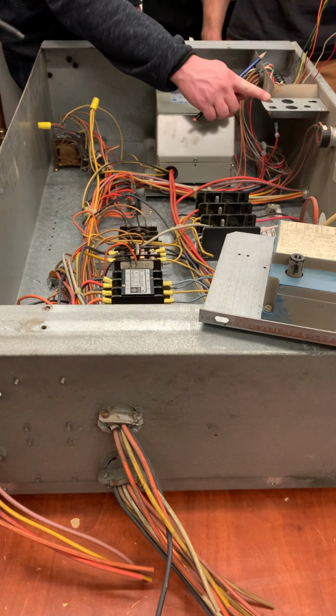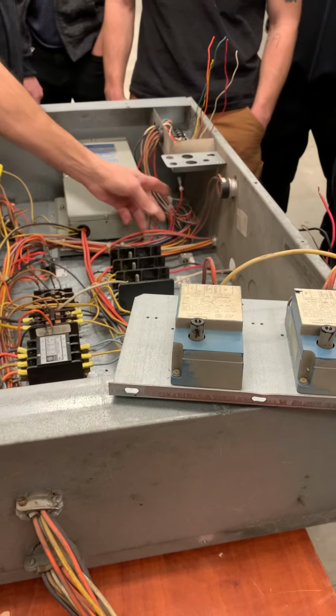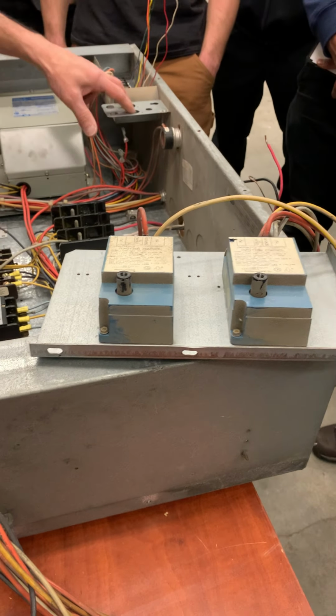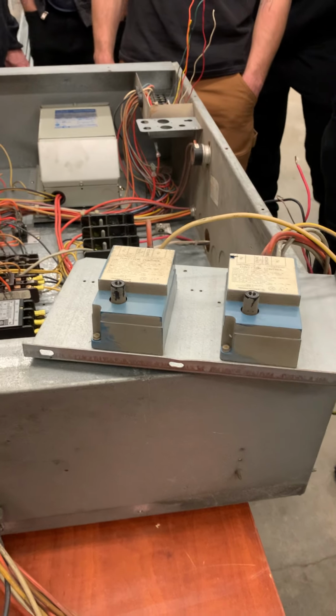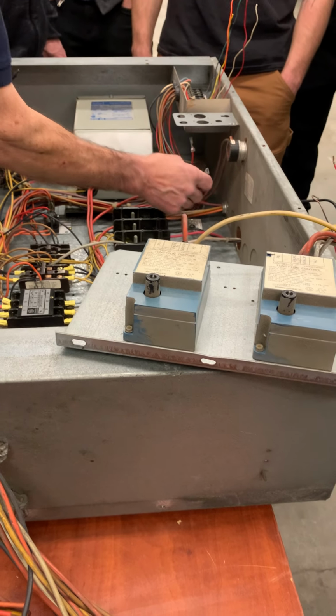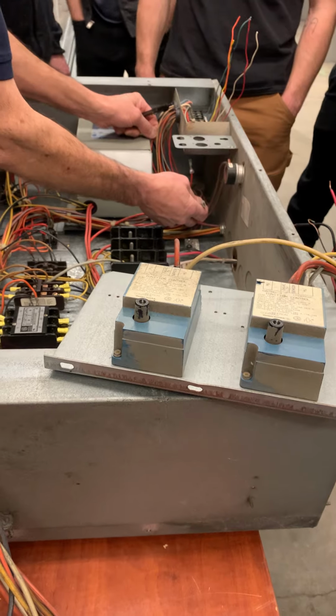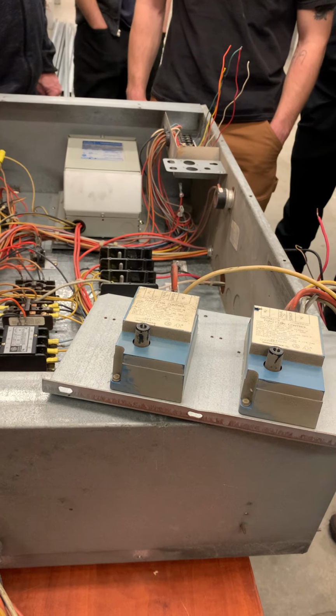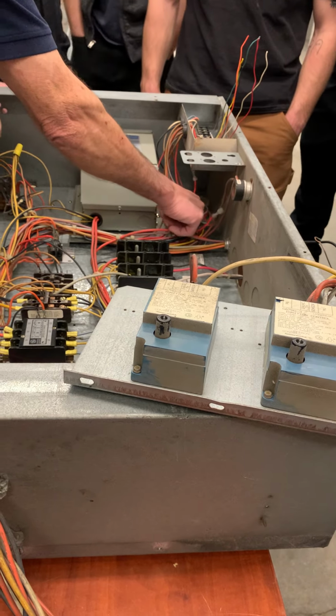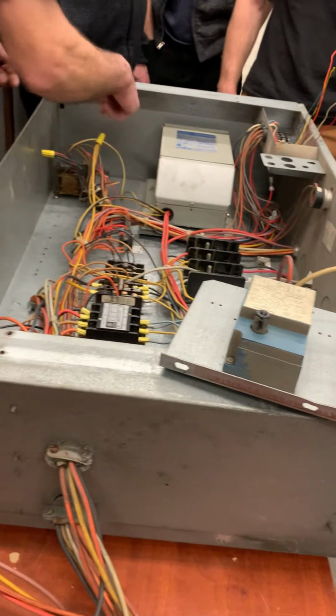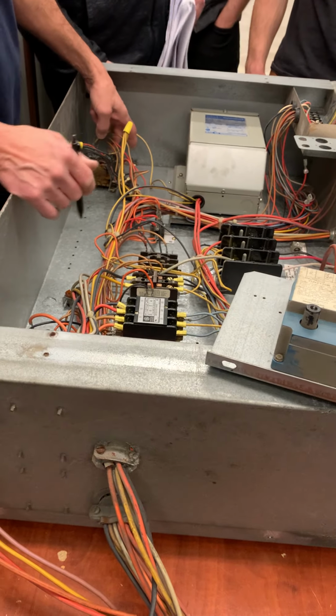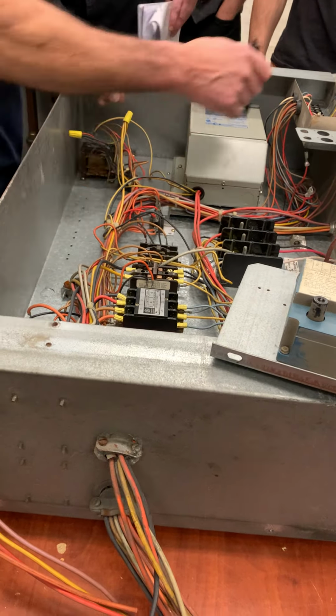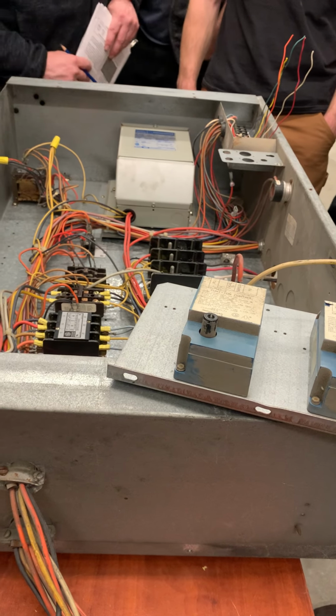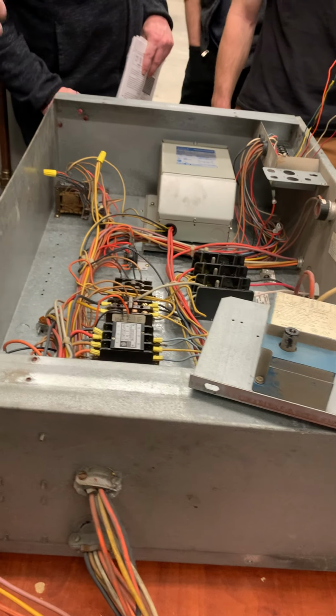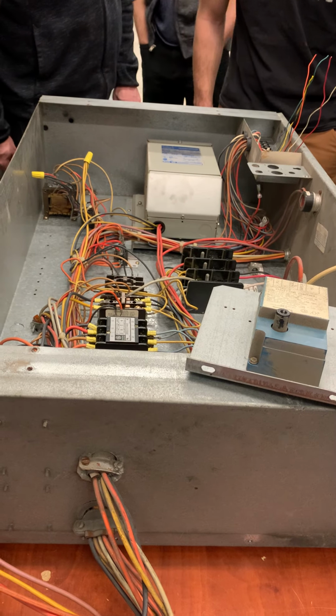Sorry, with this wiring, where does it go through here? In this area right here, I had some wires coming up. These were fuses. So that would be my fuse. I'm curious as to why that small wire is coming from here. If you look here, that one's coming to the 24 volt side. The other wire here, which is going this way, comes to this terminal. So everything coming from the transformer goes to the fuse over here. So that's going to protect my transformer. What's the VA rating on the transformer? 75. What do you think the fuse size was?